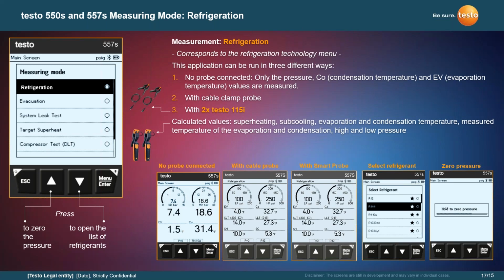So there, and then here you would also select your refrigerant to make sure you're correctly getting the right subcooling or superheat number based off the pressures and the temperature chart that are downloaded in the cloud. Again, we get a lot of people sending things back, and the service side gets it, and they were selecting, instead of 410A, they had 401 or some other refrigerant that was close to it on there, or they were selecting just the wrong refrigerant altogether. So that does happen, and always make sure you have the right refrigerant selected to get the right reading. So just remember that as well.